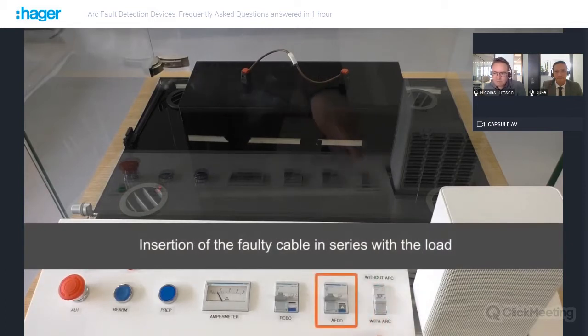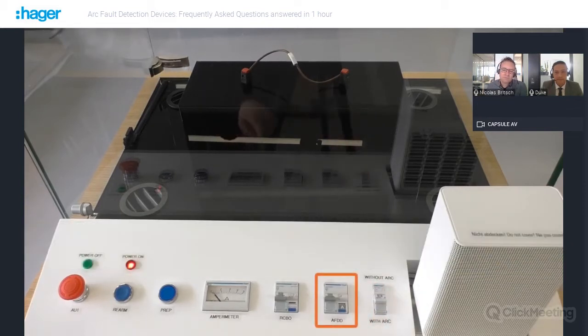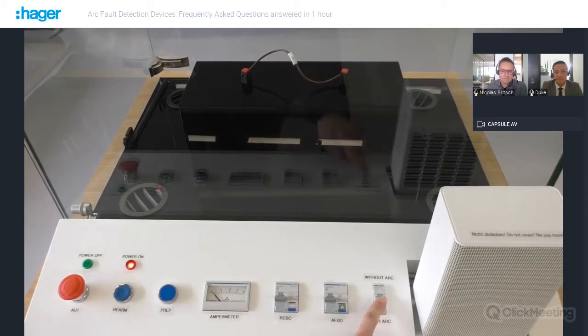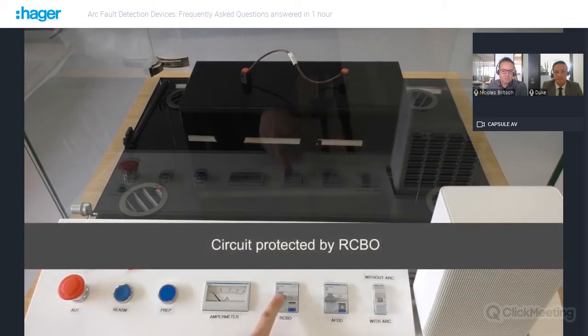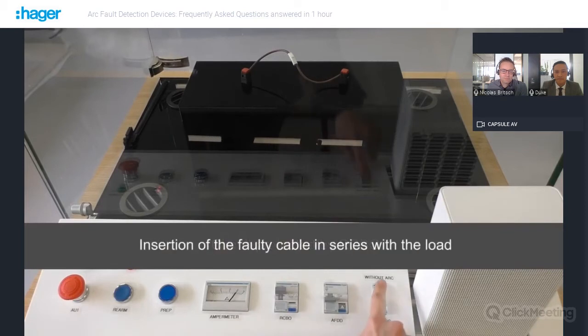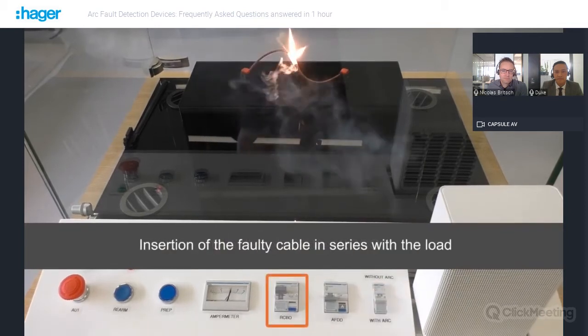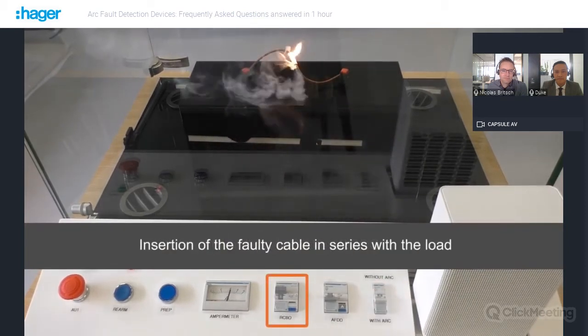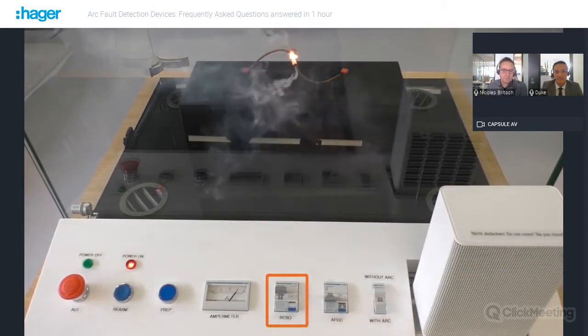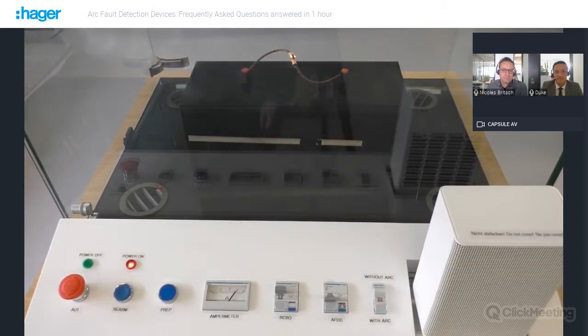The AFDD has tripped at the moment the faulty cable has been inserted in the circuit. And if we try to close the AFDD on the fault, it will trip back very quickly. And now we remove the fault from the circuit, and we will use the RCBO instead of the AFDD to protect the circuit. And now let's insert the fault again to see what happens. As you can see, the RCBO is not able to detect this kind of fault, and we can imagine the damage to surrounding materials and the spread of fire to the building.